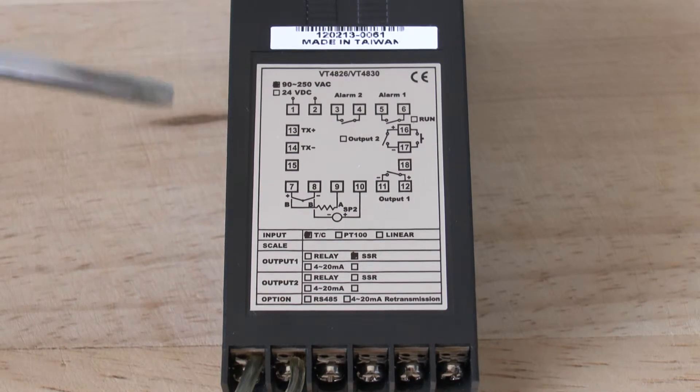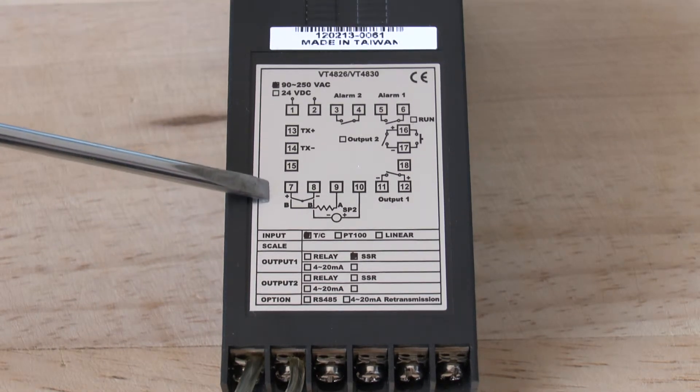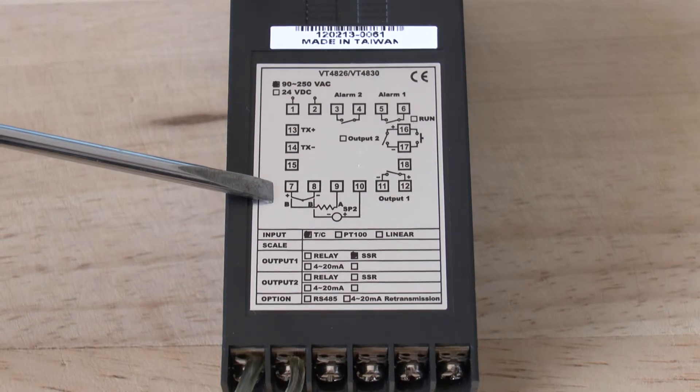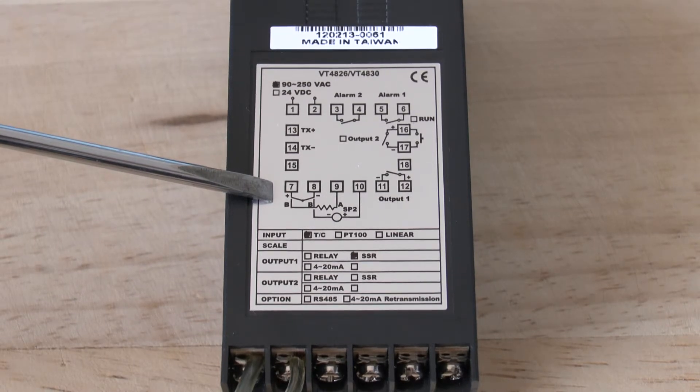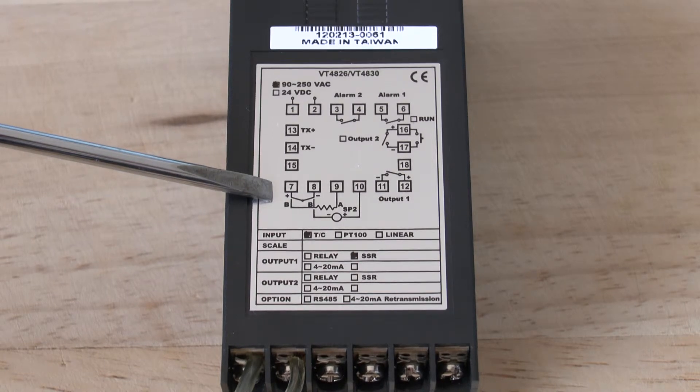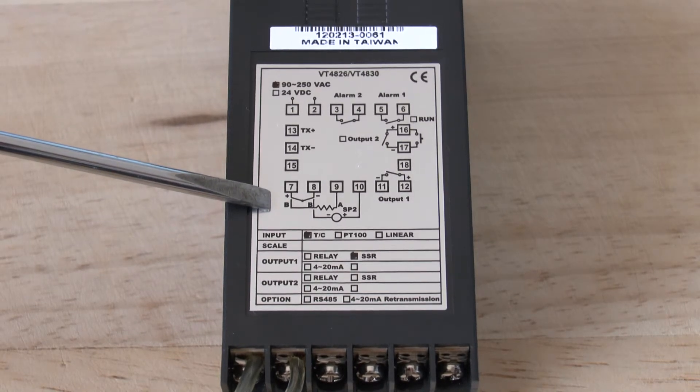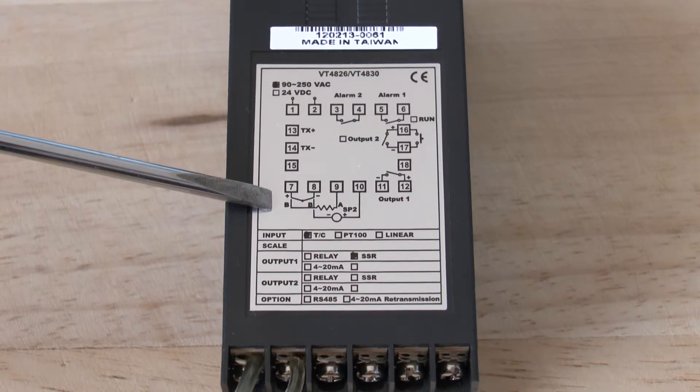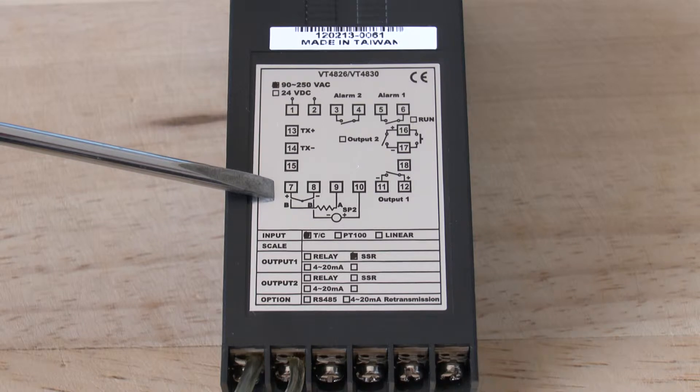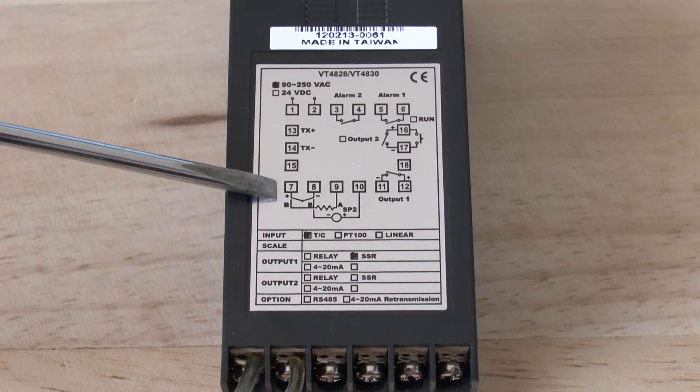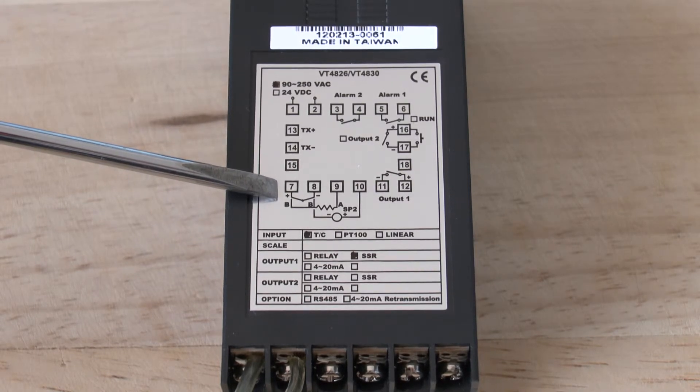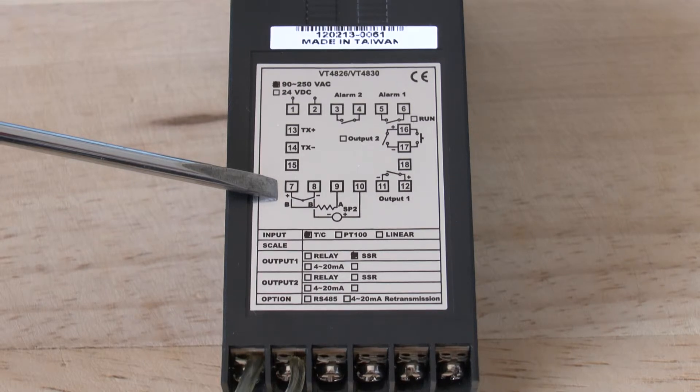The thermocouple input goes on terminals 7 and 8, terminal 7 being the positive and terminal 8 the negative. If you should have a PT100, normally it would be a three-wire device and the two similar colors go on terminal 7 and terminal 8 and the odd color will go on terminal 9.